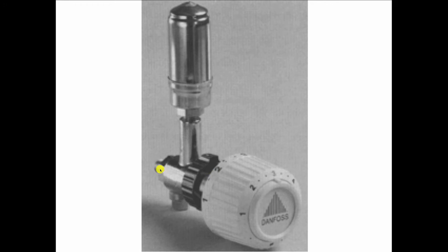So this over here would go into the radiator where the air vent would normally be. This is an air vent over here, and we like to use a straight shank air vent on here so the condensate can more easily drip out. This is a normally open spring-loaded valve, and onto this screws this temperature-sensitive head. So this is going to sense the temperature in the room. We have it set for 3, which would be 70 degrees Fahrenheit.